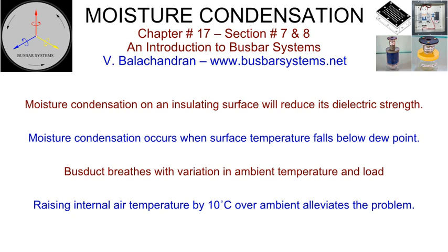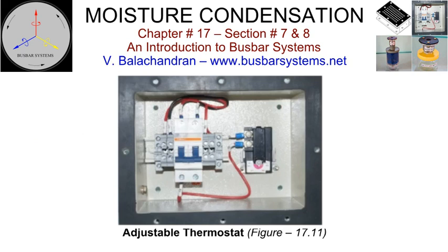When a metal enclosed air-insulated bus has remained in de-energized condition for a sufficiently long time, to hasten the commissioning process, it may be advisable to use portable hot air blowing equipment to remove the moisture and dust before the heaters are switched on. It is, therefore, the normal practice to install anti-condensation heaters inside the enclosure to elevate the temperature of the air above the dew point.